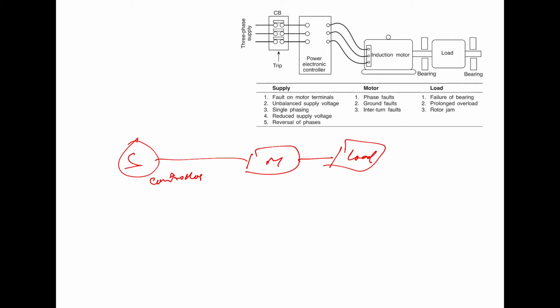So the induction motor is subjected to a large number of faults and abnormal operating conditions. This table shows the faults and abnormal operating conditions of the induction machine. On the supply side: fault on the motor terminals, unbalanced supply voltage, single phasing, reduced supply voltage, and reversal of the phases. On the motor side: phase faults, ground faults, and interturn faults. And on the load side, we have failure of the bearing, prolonged overload and rotor jam. So you have to take this into consideration while considering any protection scheme for this induction machine.